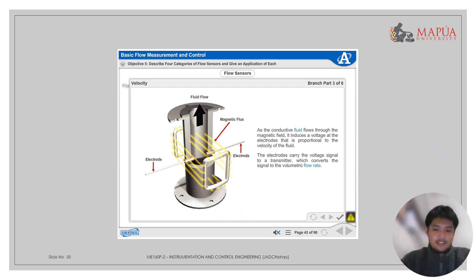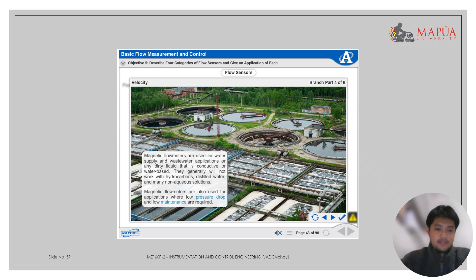Magnetic flow meters are used for water supply and wastewater applications or any dirty liquid that is conductive or water-based. They generally will not work with hydrocarbons, distilled water, and many non-aqueous solutions. Magnetic flow meters are also used for applications where low pressure drops and low maintenance are required.